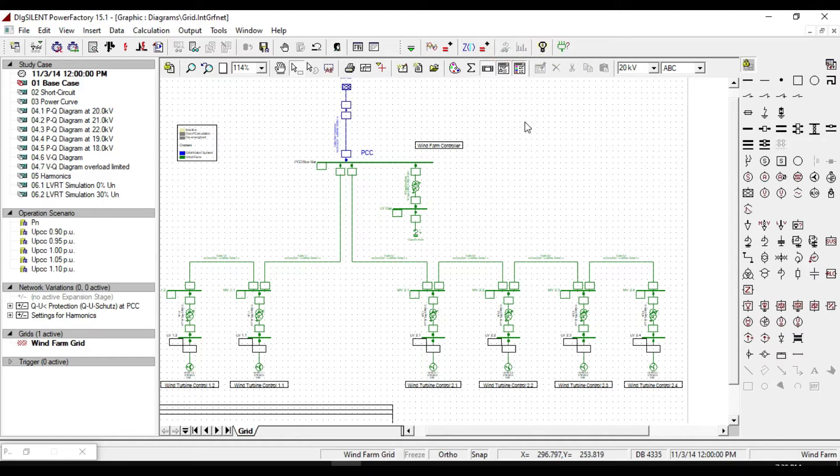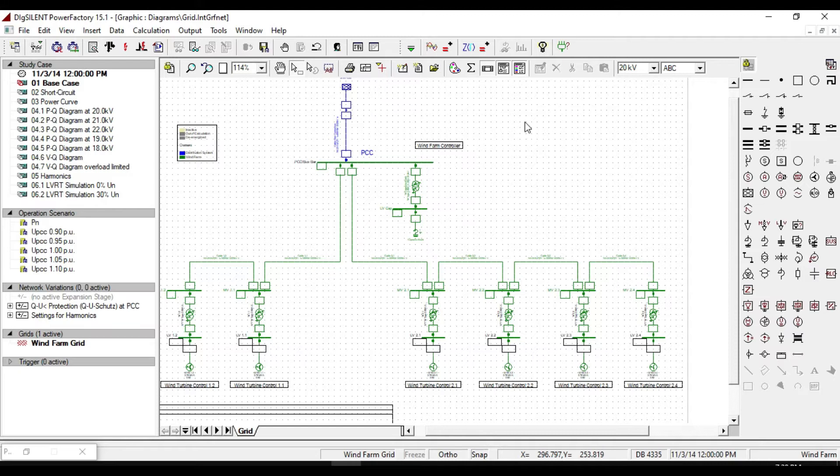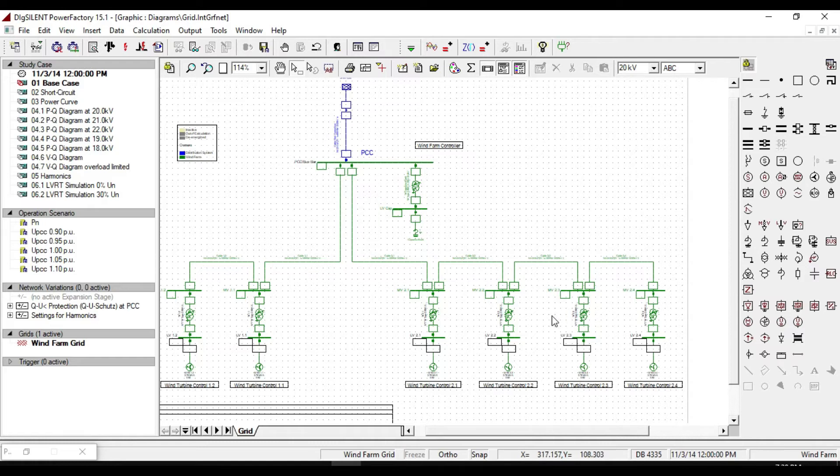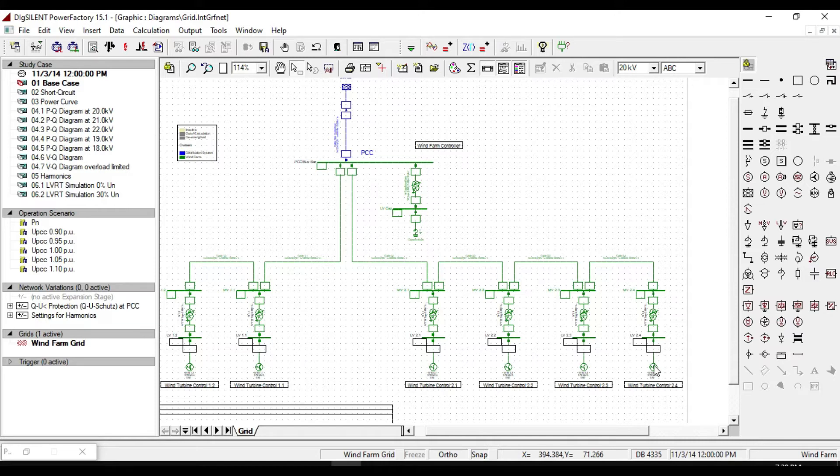Before performing power quality and harmonic analysis, it is needed that all the elements in the network system must be modeled accurately, and all the harmonic models and non-linear loads should be determined. It is also needed to determine the exact model of elements such as the wind turbine which feeds harmonics to the network system.